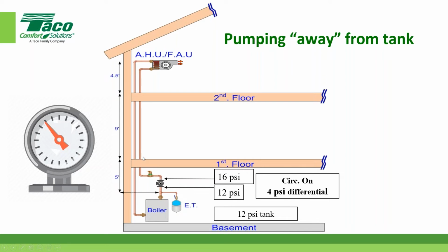Okay, now it comes up here, it starts to get eaten away with friction loss and the weight of the fluid traveling up, okay? But it's still upwards of 16 PSI. I gain some PSI by coming down, but I get a little bit taken away on friction loss. Ultimately, by the time I get back to this point right here, I'm back at 12 PSI. So everything the circ's adding gets used up within the pipe, the valves, the fittings, and the friction loss of the system. Hopefully, this two-dimensional sketch will give you a better idea of why we want to pump away from the point of no pressure change.